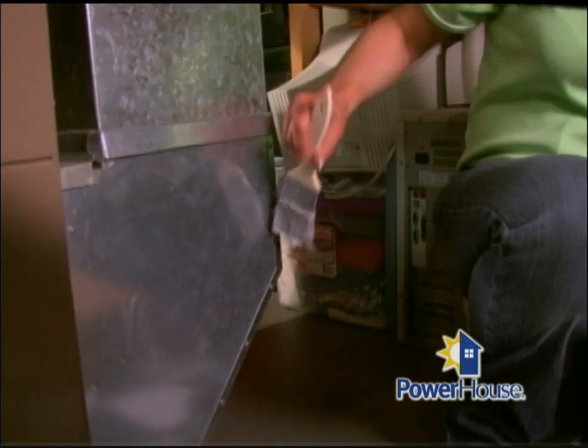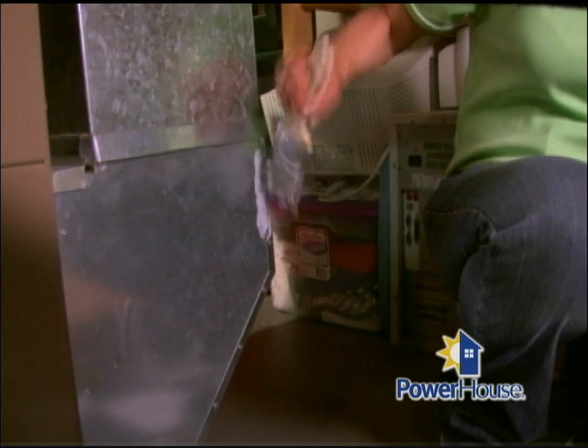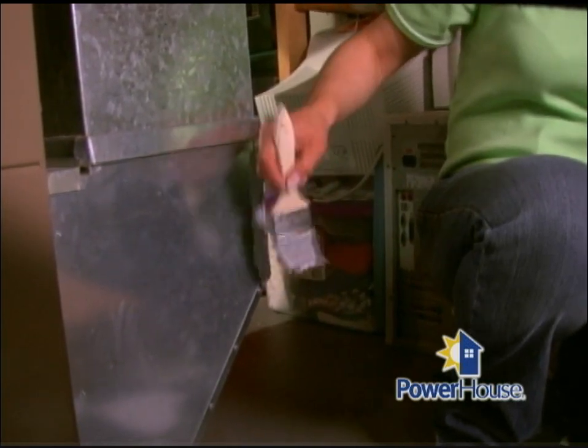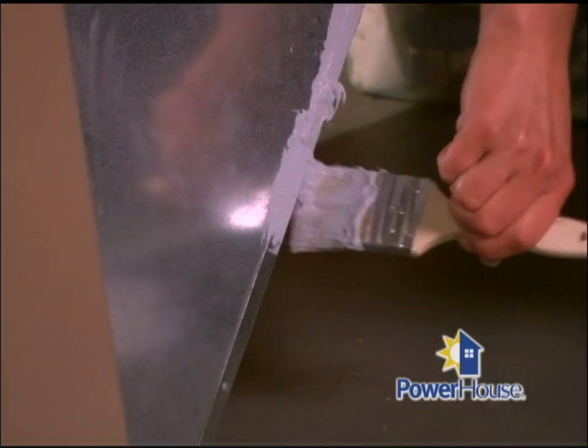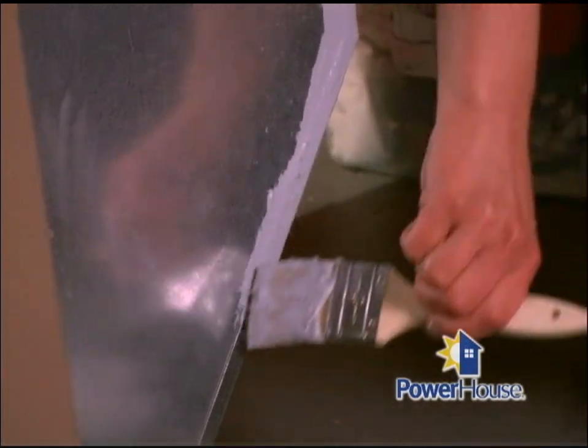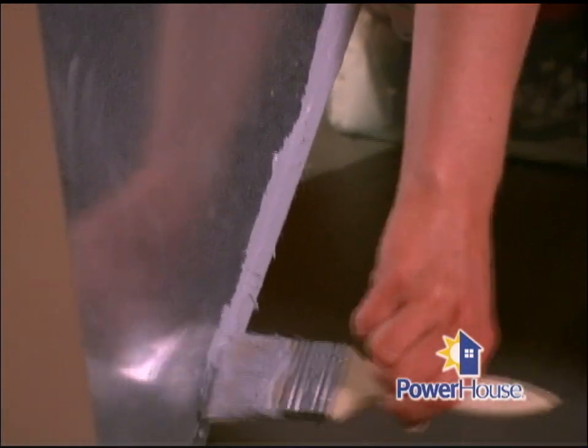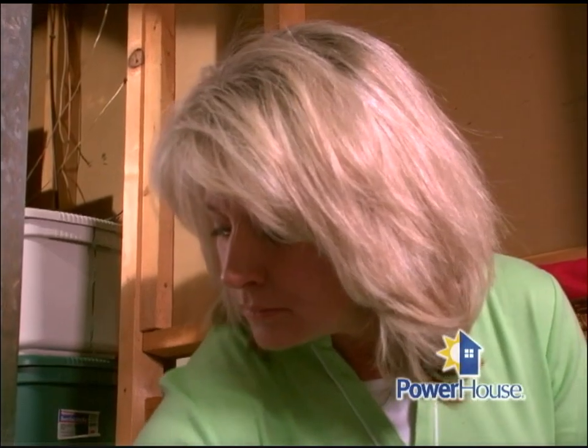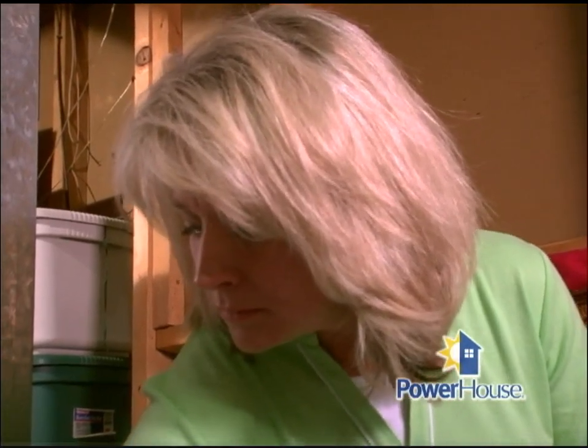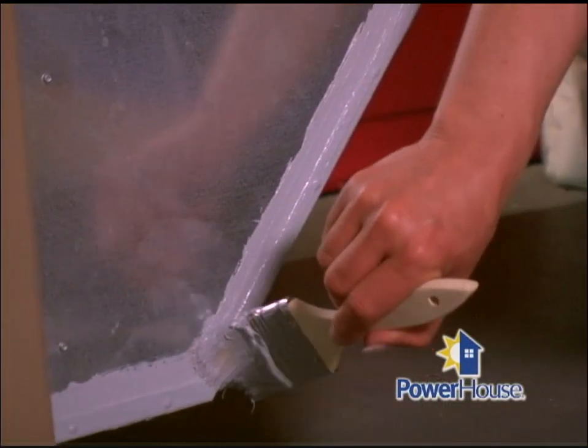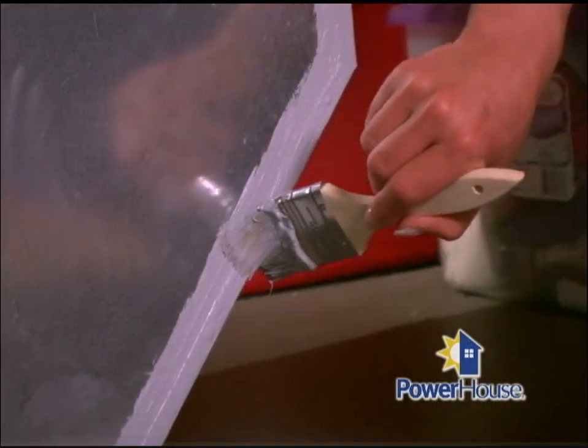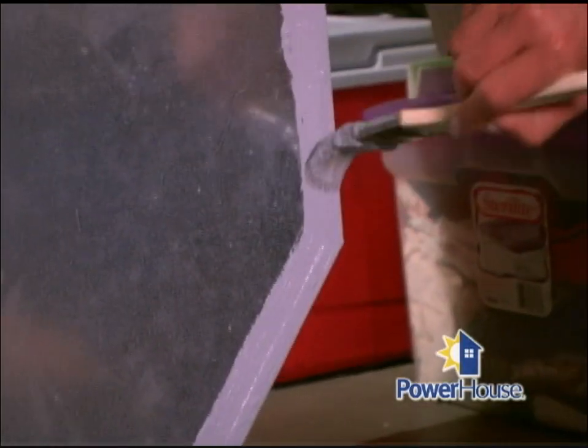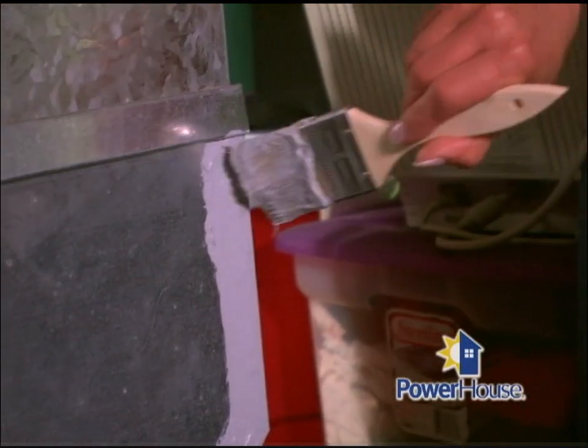Because the use of mastic is still fairly new, it may not be widely available in your area. We had to purchase ours from a local heating contractor. It dries quickly and remains flexible after it is cured. 1 gallon covers roughly 300 linear feet. Openings to be sealed should not exceed 1/8 of an inch. For wider gaps, it's recommended that you apply the mastic over mesh tape or sheet metal for additional reinforcement. The most common way to seal your ductwork is with tape.